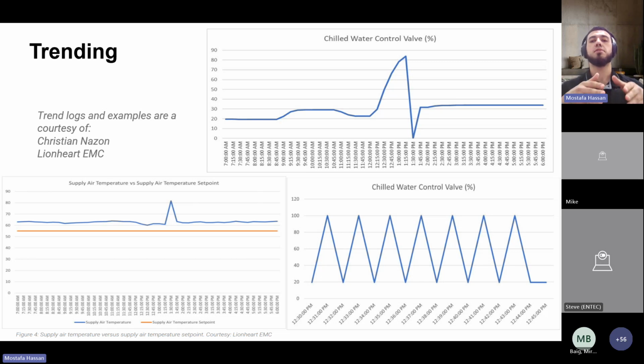Right, this is going to help guide the process of selecting the right data points for trend. Right? You can't just trend every point and put it on whatever intervals you want. It has to be necessary to actually optimize the system. Right. To add more context to this air handling unit sequence of operation, in this case, we're going to outline the parameters of the economizer and chilled water control. Right? Differential dry bulb economizer control was implemented here.